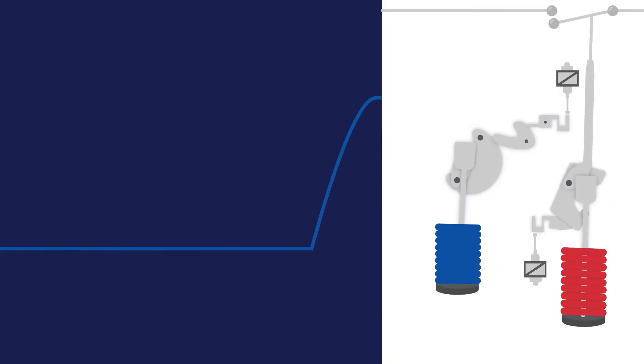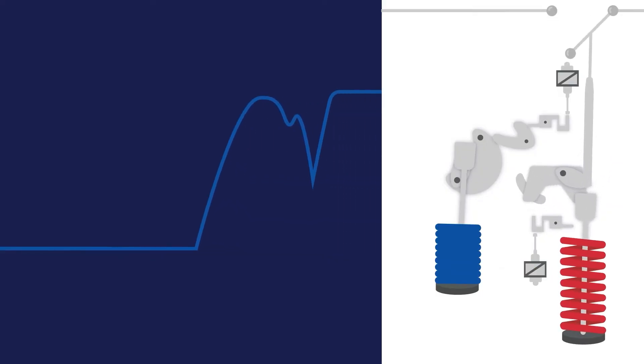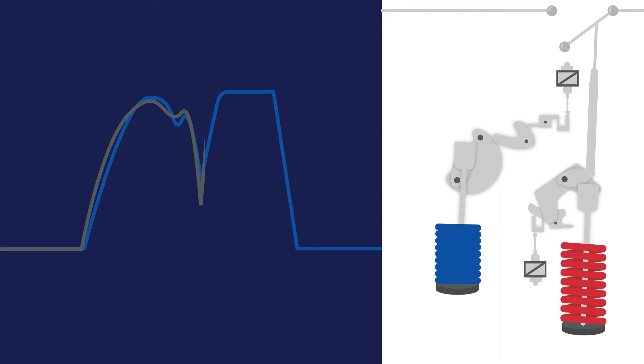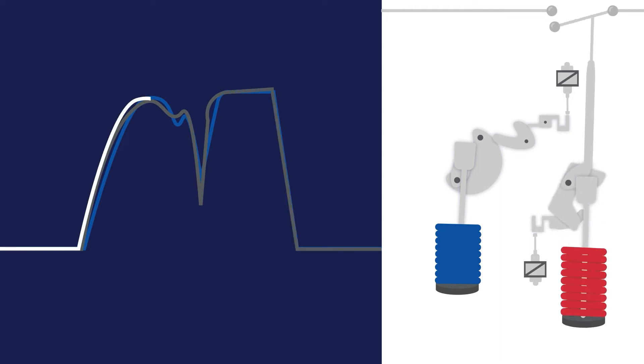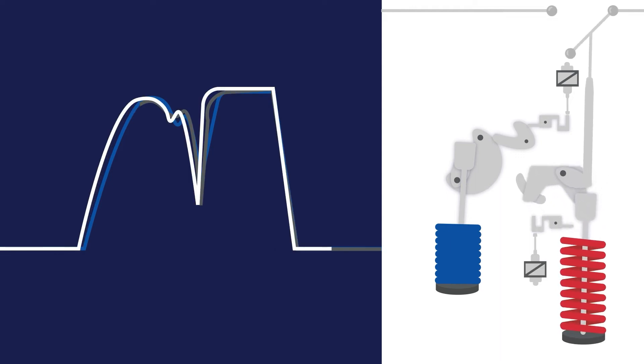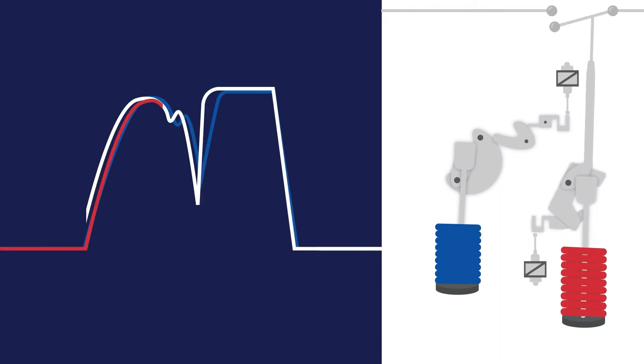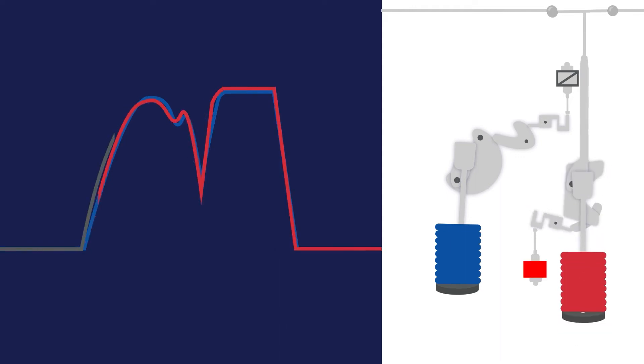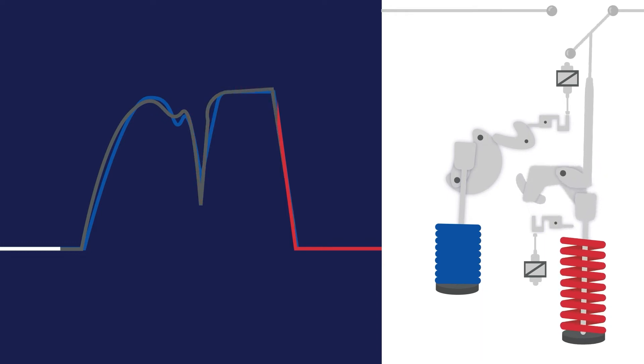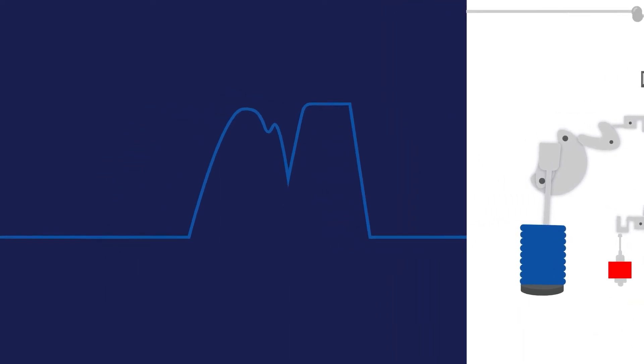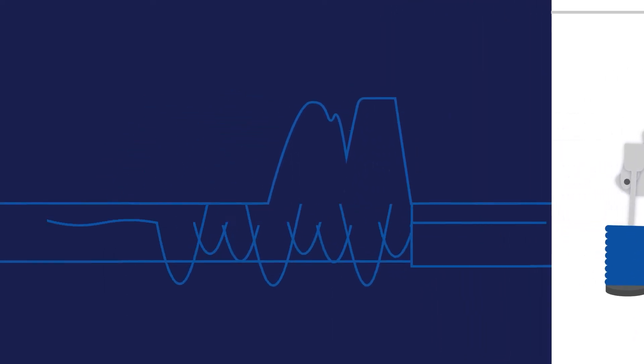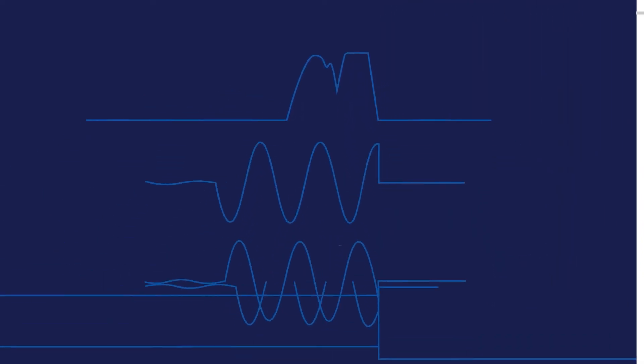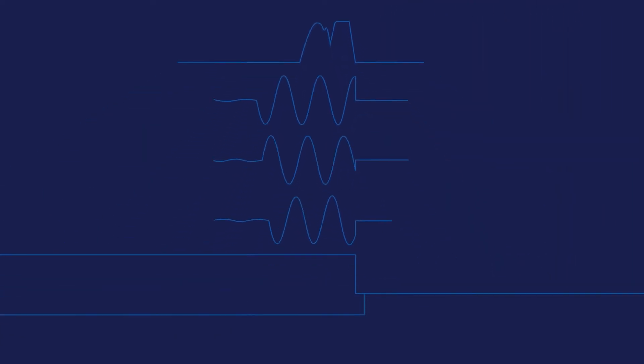The switchgear monitor captures this waveform and uses it as a baseline fingerprint for normal operation. This provides a reference for comparison of future trip operations and allows for a detailed diagnosis of any variations of breaker performance.